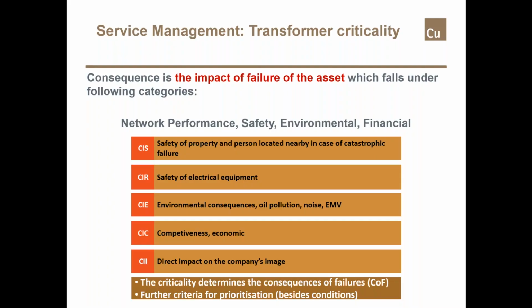And while doing the transformer as a key asset into the distribution sector, while doing that asset management and meeting our KPI, the consequence is the impact of failure of the asset in these blocks, the safety of property and the person located nearby in case of catastrophic failure, the safety of electrical equipment. We very recently came across a very unfortunate incident into Andhra, Srisailam. The environmental consequences, the oil pollution, noise, EMF, all this. If we have failures, the competitiveness and the economic reasons, and the direct impact on the company's image.